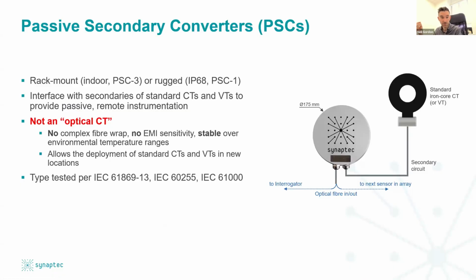They're converting the secondary of the CT or VT that's connected to it into an optical measurement. And they're doing that without any local power supply, without any local time synchronization signal, and with no digital telecoms access. Just to stress again, this is nothing like an optical CT. So we require no complex fiber wrap, which is susceptible to error. We have no sensitivity to electromagnetic interference, and we're stable over environmental temperature extremes. So this method really then allows the deployment of tried and tested CTs and VTs in new locations over very wide areas without the extreme costs of deploying a new substation to support that infrastructure.